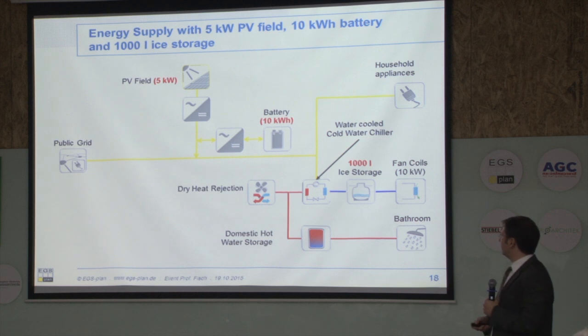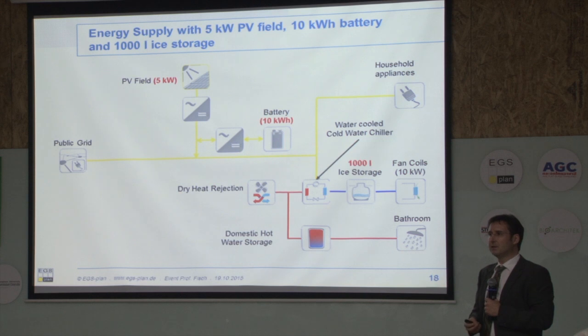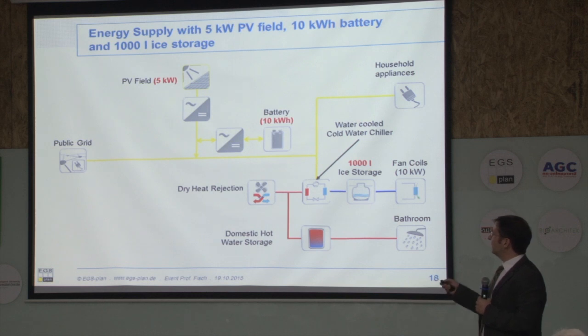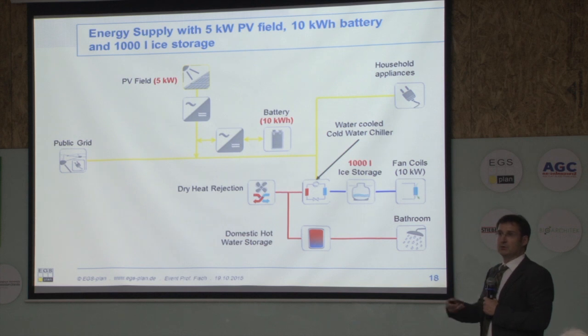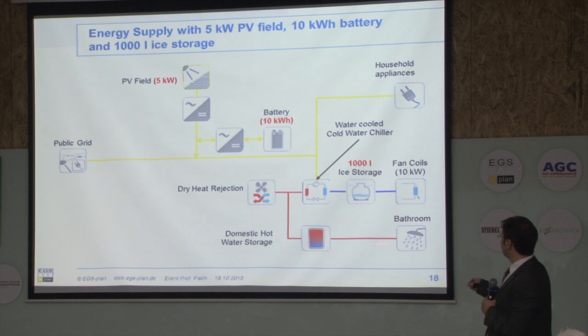So we decided to go for ice storage, because an ice storage can store much more thermal energy due to the phase change which is taking place. So what we are doing now in that building is during daytime we produce a lot of electric energy from the PV field. We supply it to the battery, we charge the battery, and at the same time we are running the chiller. The chiller produces ice for the storage, and at the same time it also produces hot water, which is stored in the domestic hot water storage, so we can use it later in the bathroom for taking a hot shower.